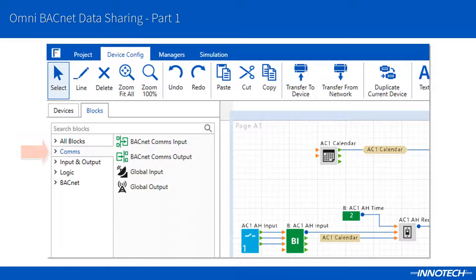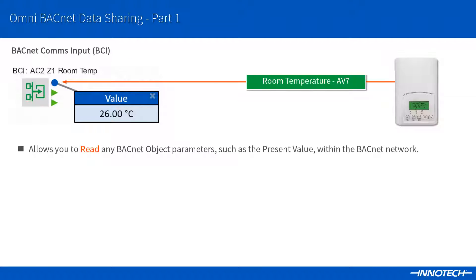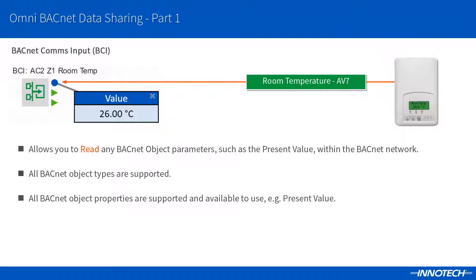In the Focus programming software, you can access the BACnet Comms blocks via the Comms group. This consists of the BACnet Comms Input or BCI and the BACnet Comms Output or BCO. These blocks allow us to configure the BACnet data sharing options within OMNI and external objects on other BACnet devices. The BCI block allows you to read back any supported BACnet object and property value. There are many property types to select from as listed by the BACnet standards, and the most common property used is the object's present value, which provides the actual value reading of the object.